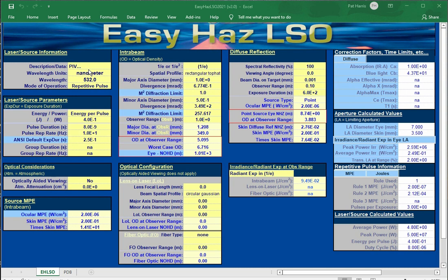The reason is when the first pulse is absorbed by your biological tissue, if the second one is absorbed within 5 microseconds, there has not been enough time for the heat to move away from the energy absorption of the first pulse. So all the heat is still sitting right there where the pulse was first absorbed. The second pulse comes in, and so you are just adding twice the energy, creating twice the heat. Once you're past 5 microseconds, the heat will start migrating out. But within 5 microseconds, the heat doesn't have time to move. It's called thermal confinement.